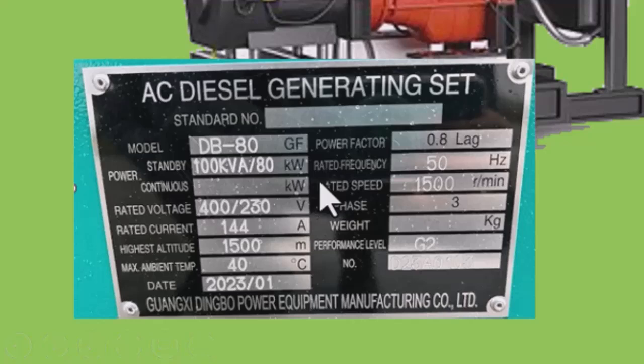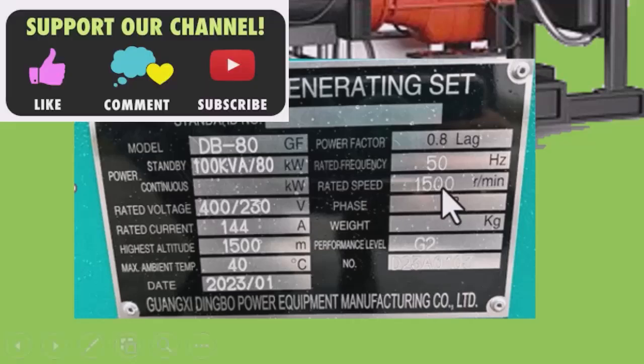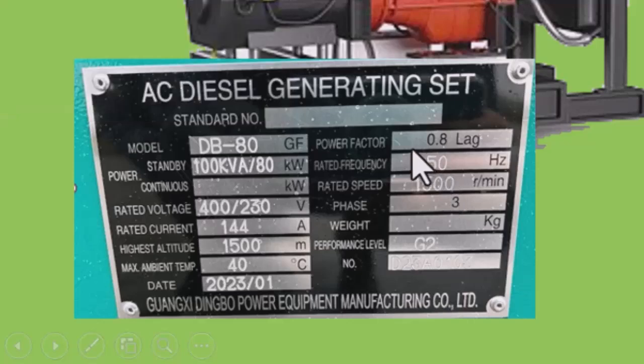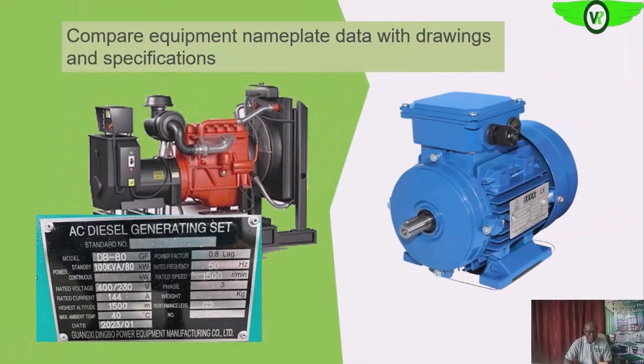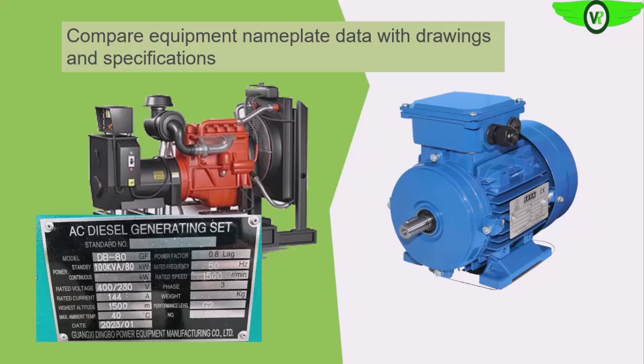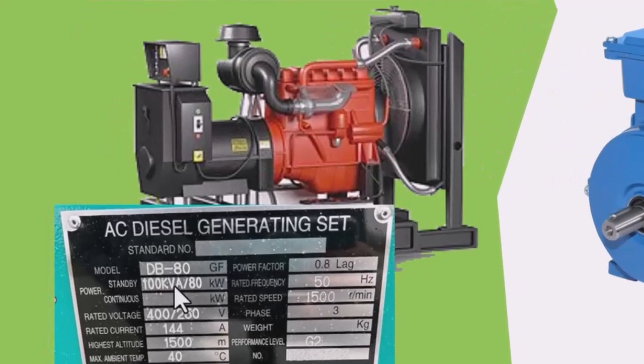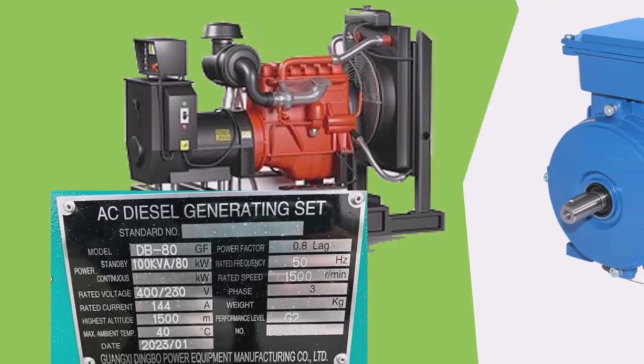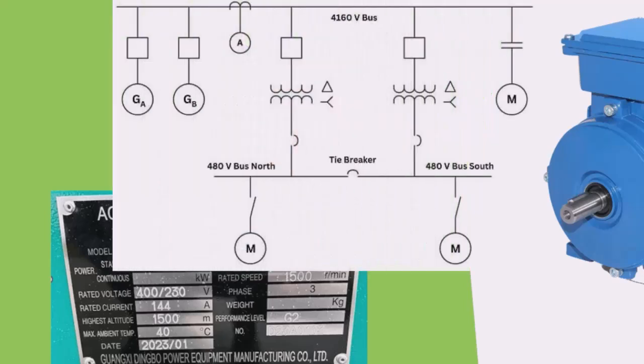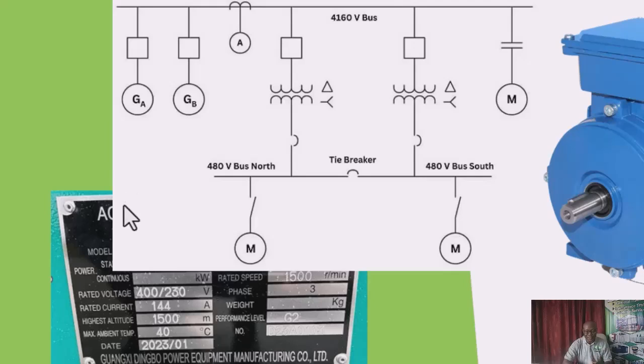Okay, then if you look at the specifications, maybe the speed, the RPM, we may have it specified. And if you look here, you see the RPM. Then the frequency of operation, we also have them specified, and the number of phases, 3 phase. Okay, all of this may have been specified. Then the environment where we use this equipment actually determines the ambience. The ambient temperature should be less than 40 degrees Celsius. So when we compare this information with what we have on the specification sheet, that will tell us if what we are procuring or what we are installing is what we actually needed in our installation. Then we can also compare it with the drawings.